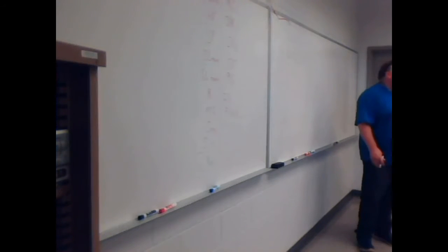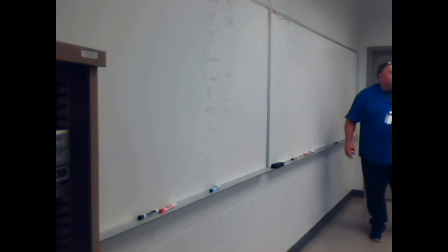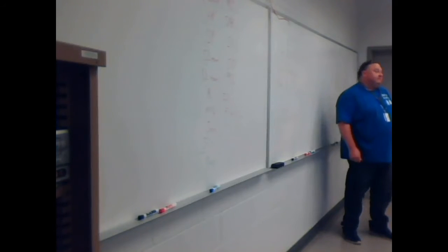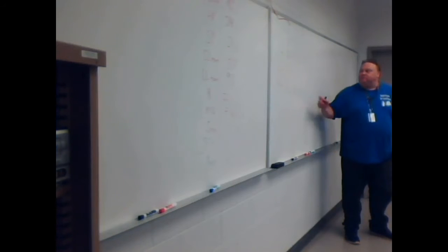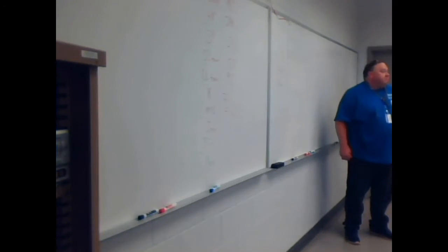So if you've got a TXV in that spot, then I don't really use superheat to figure it out, only if I'm trying to see if the thermostatic expansion valve itself is bad. If we've got a fixed device, cap tube, piston, orifice, then we care. Is everything going to TXV? Pretty much. It could be efficiencies.